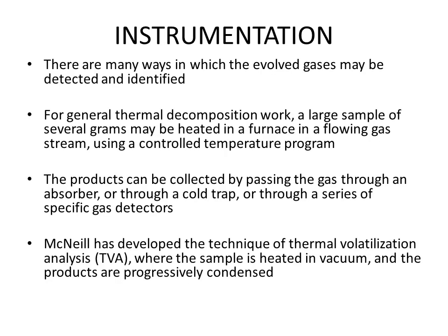There are many ways in which the evolved gases may be detected and identified. For general thermal decomposition work, a large sample of several grams may be heated in a furnace in a flowing gas stream using a controlled temperature program. The products can be collected by passing the gas through an absorber, through a cold trap, or through a series of specific gas detectors. These are the methods of collection of products in the form of gas.